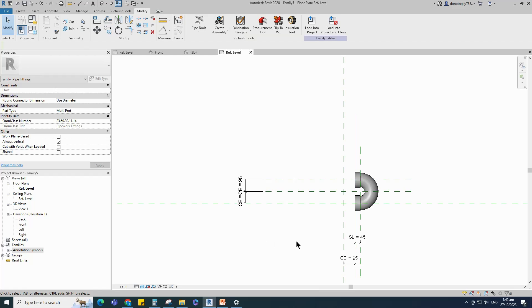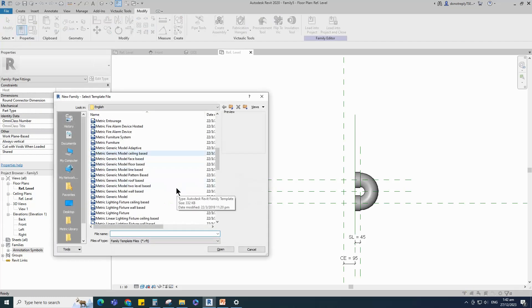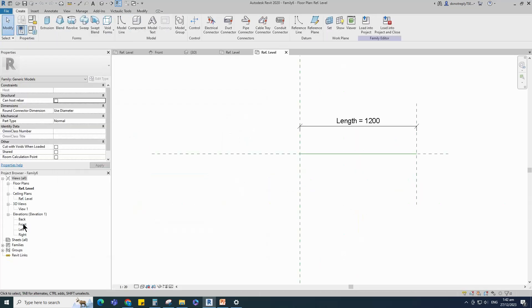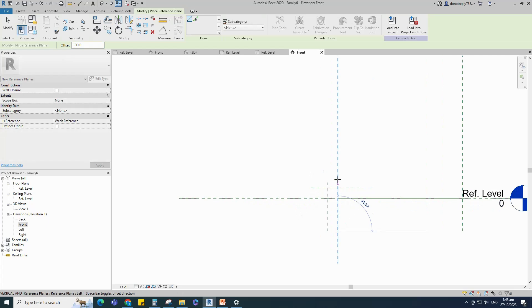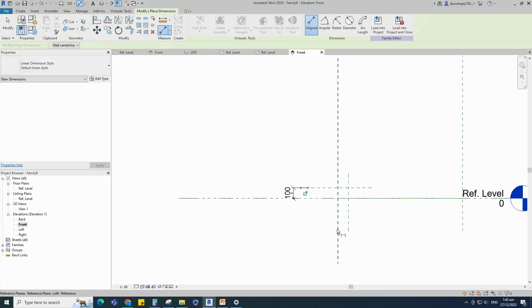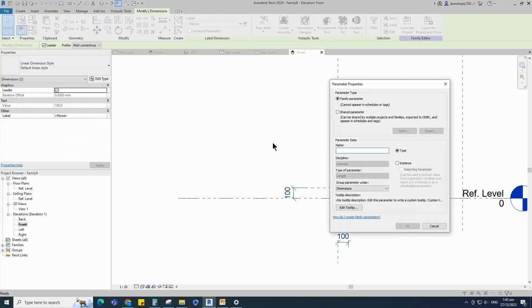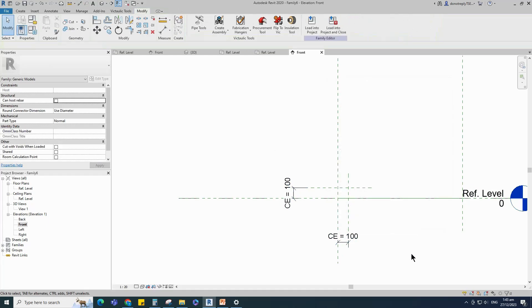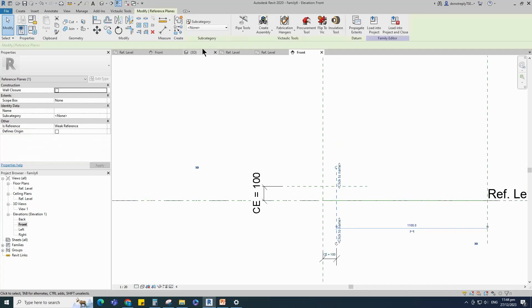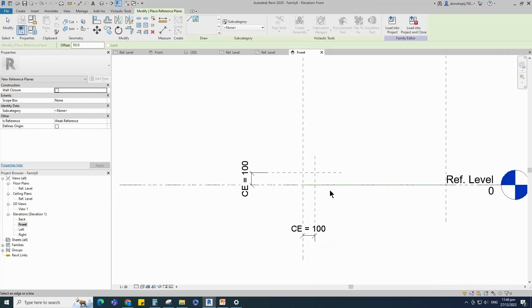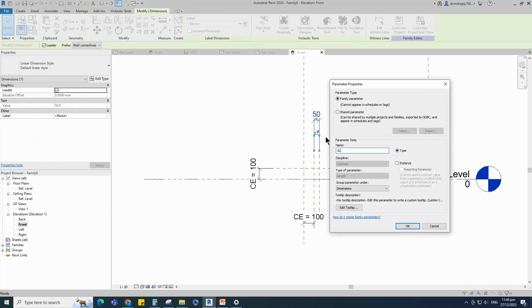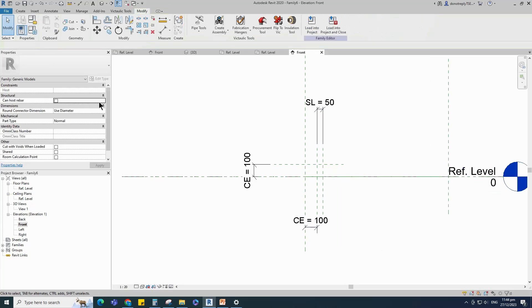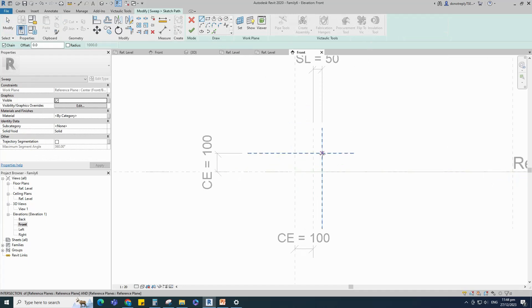To create the P-trap elbow family, open a new family. Select the generic model line-based and open it. Go to front view. Select the existing reference plane, offset 100mm and create similar. Insert a dimension. Select the dimension and add parameter for CE — select instance and click OK. Select the existing reference plane, offset 50mm and create similar. Insert a dimension and add parameter for SL. Go to Create, select the sweep, sketch path.